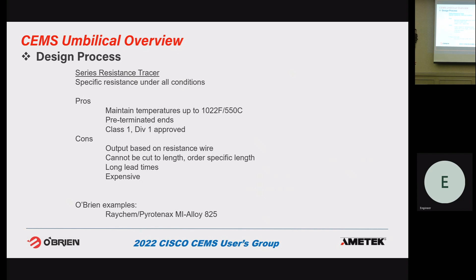then the next style is series resistance, which is where we use an MI. Everybody know what an MI tracer is? It's used in the field a lot. It looks like a metal tube. It has either one or two heater elements in it. Really, really high maintain and exposure temperature. The real downside about MI tracer is you buy it as a specific length. It already has end terminations and power connections built onto it. If you cut it, it's a very difficult repair to make. So you buy it at a specific length, and it's really made for field install. It doesn't lend itself so well to tubing bundle.